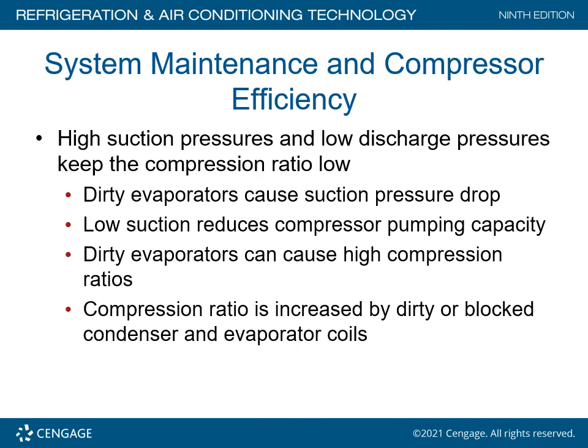For system maintenance and compressor efficiency: high suction pressures and low discharge pressures keep the compression ratio low. Dirty evaporators cause suction pressure to drop — low suction reduces compressor pumping capacity and causes high compression ratios. Compression ratio is increased by dirty or blocked condenser or evaporator coils. Bottom line: you must have a clean evaporator coil and a clean condenser coil for the system to operate at peak efficiency.